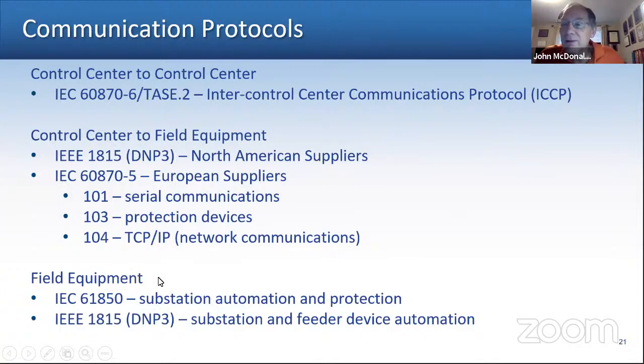Then down in the field, if it's a North American supplier, we'd still use DNP3 or IEEE 1815, but truthfully, the global worldwide standard for substation automation and field communications is IEC 61850. So the beauty of this is we've gone from many different choices to converging on just a few.